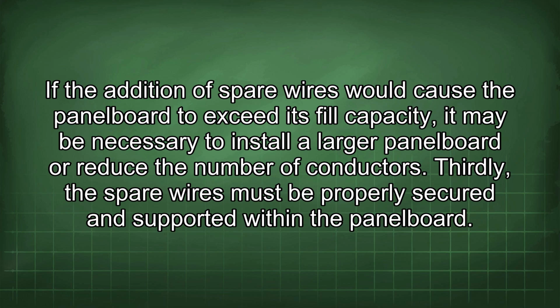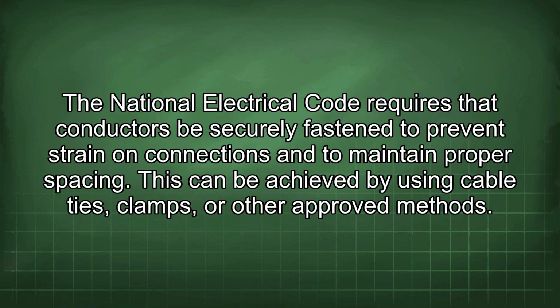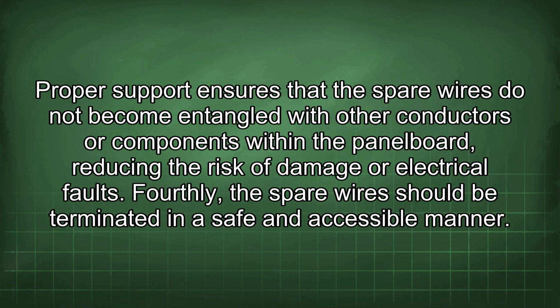Thirdly, the spare wires must be properly secured and supported within the panel board. The National Electrical Code requires that conductors be securely fastened to prevent strain on connections and to maintain proper spacing. This can be achieved by using cable ties, clamps, or other approved methods. Proper support ensures that the spare wires do not become entangled with other conductors or components within the panel board, reducing the risk of damage or electrical faults.